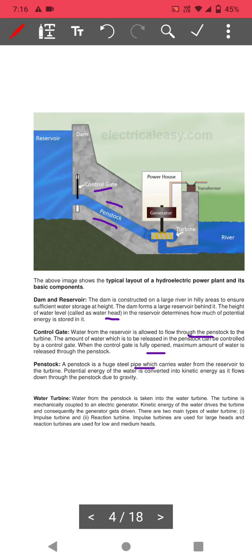Potential energy of water is converted into kinetic energy through the penstock due to gravity. Water from the penstock is taken to the water turbine, which is mechanically coupled to the electrical power generator. The kinetic energy of water drives the turbine, which continuously generates electricity. There are two main types of water turbines: impulse turbines, used for large heads, and reaction turbines, used for low and medium heads.